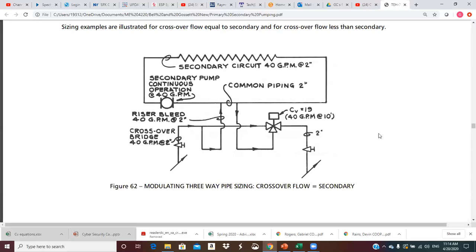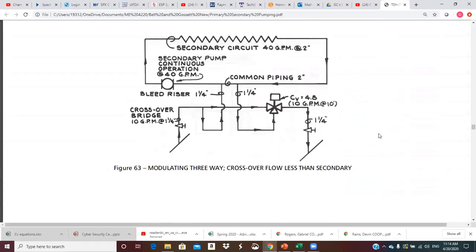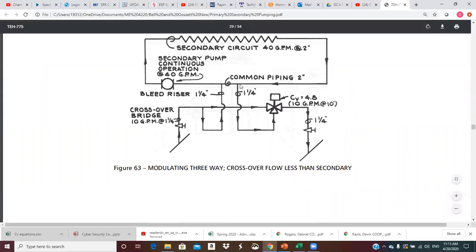For the heating situation, the crossover bridge is sized for 10 GPM and the secondary is circulating 40 GPM. Whatever is carrying 40 GPM needs two-inch pipe; whatever carries just 10 GPM can be inch-and-a-quarter. All the crossover bridge and bleed riser piping is inch-and-a-quarter. The control valve could be inch-and-a-quarter or one inch depending on what the control valve manufacturers have to offer for the required CV.